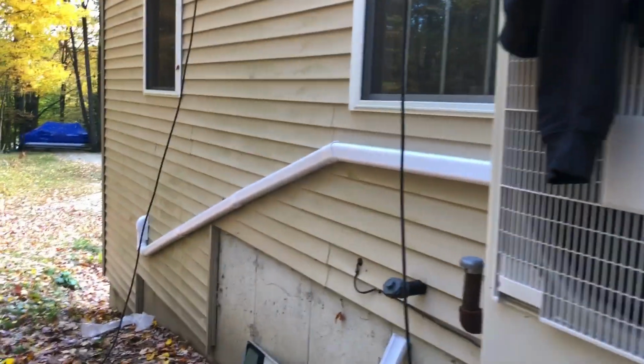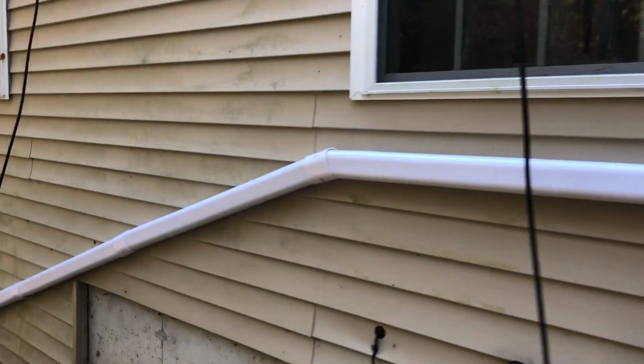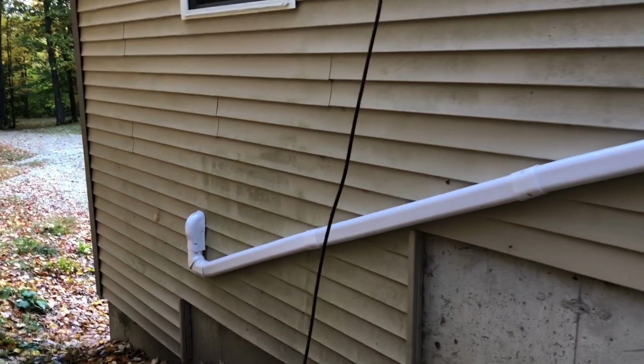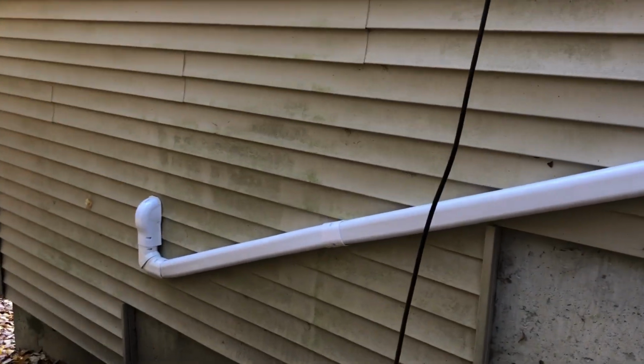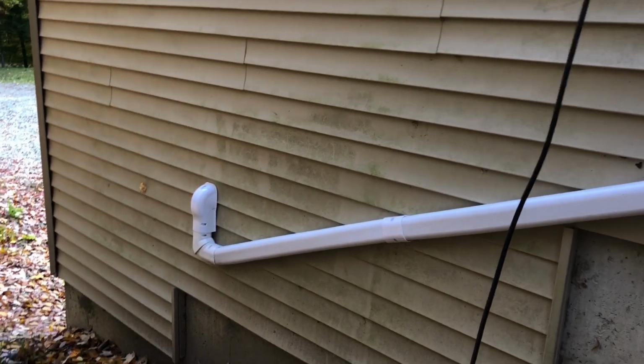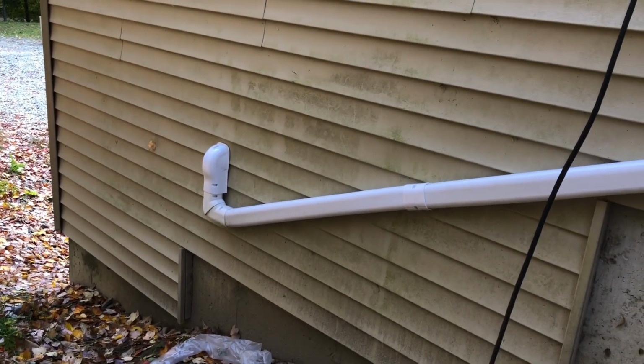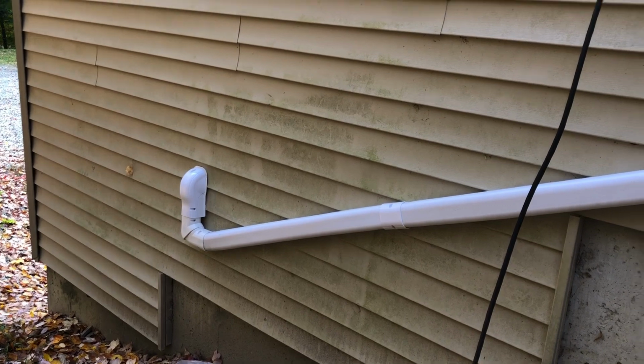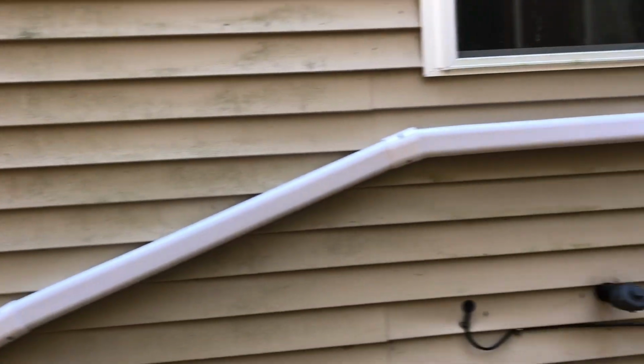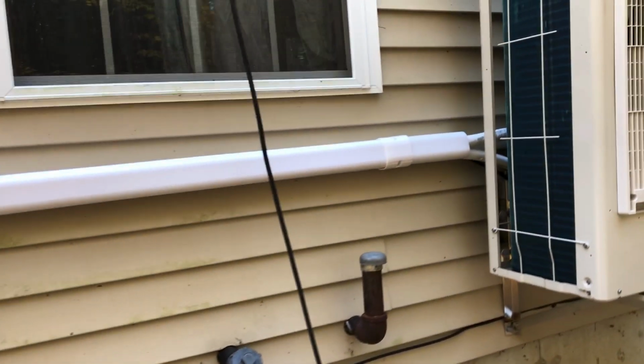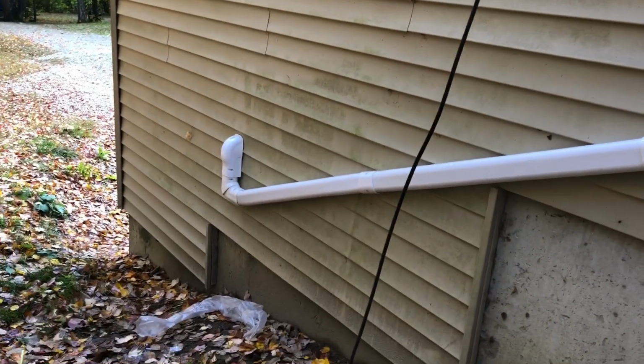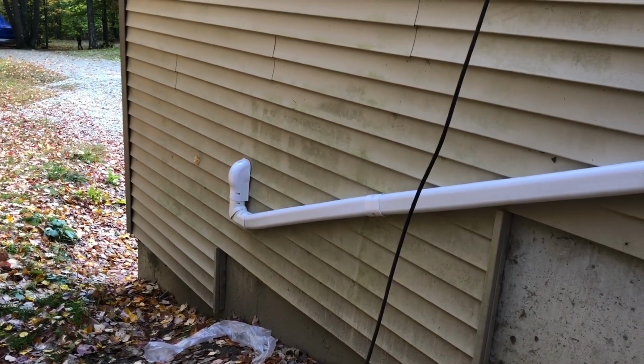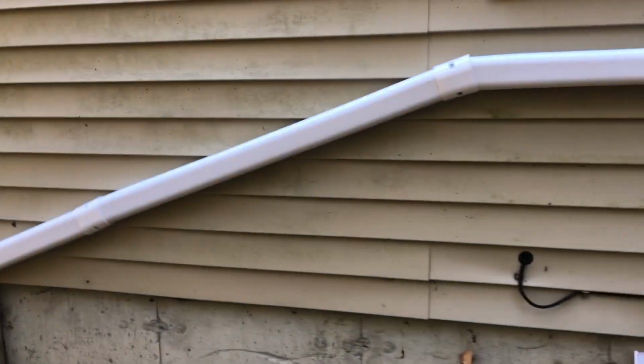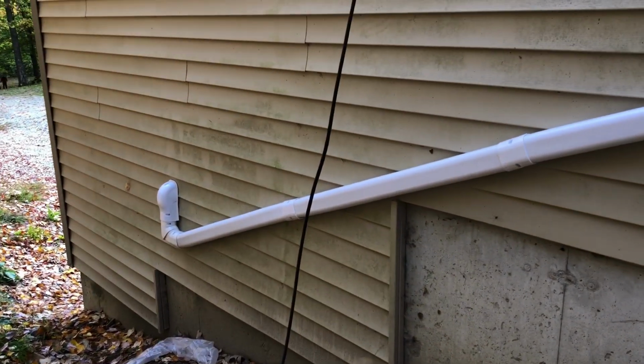Okay, so I connected the first unit. I actually ended up covering it completely with line set covers prior to showing this to you, because I had a hard time making this bend, and the covers were necessary for me to run my lines. It made it a lot easier for me. But all you got to do is connect the 2 ends from your line set, so it's pretty self-explanatory. I'll pop that cover back off when we do a pressure test, so I can see the fittings.